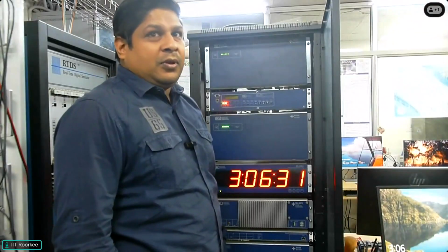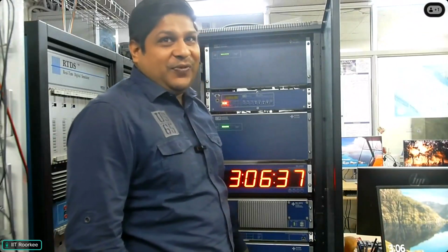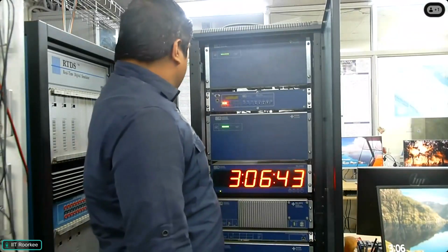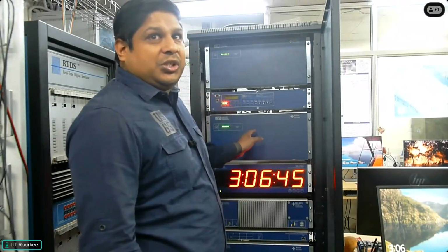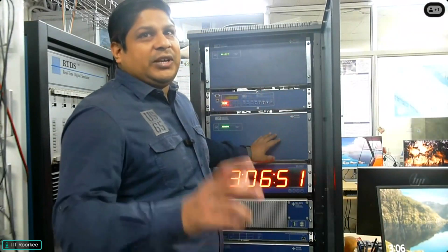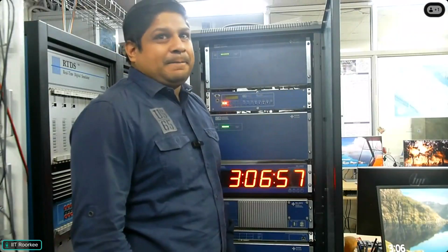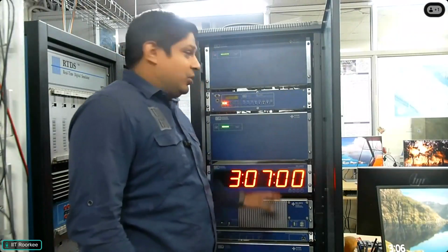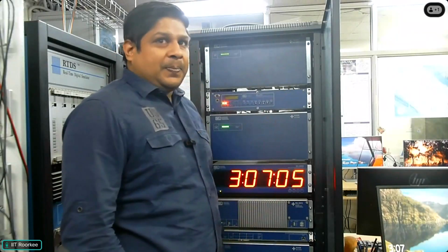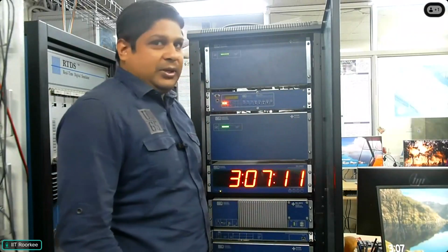What if we have to simulate more PMUs? Yeah, so for that we should have more amplifiers, or you can go directly using the GTNET card. That is connected to a switch and the switch is connected to this PMU. So directly through a communication channel we can do it, but that is a kind of simulation. There are no hard signals there. So we directly connect to this, directly to the PDC. So we can mimic that there are n number of PMUs out there. So that we can do here.